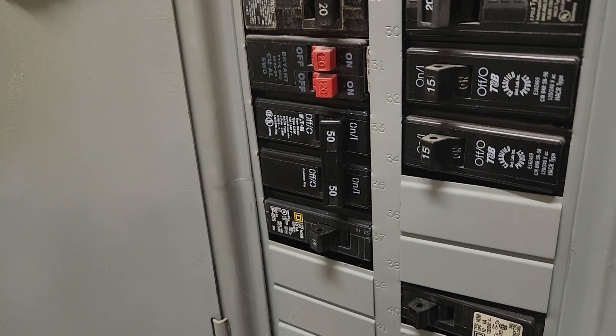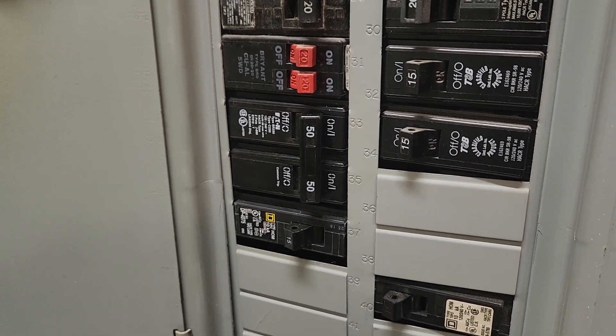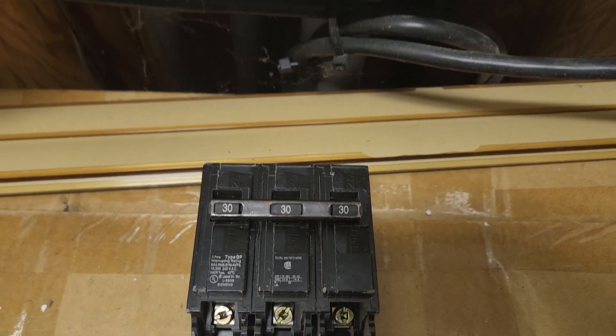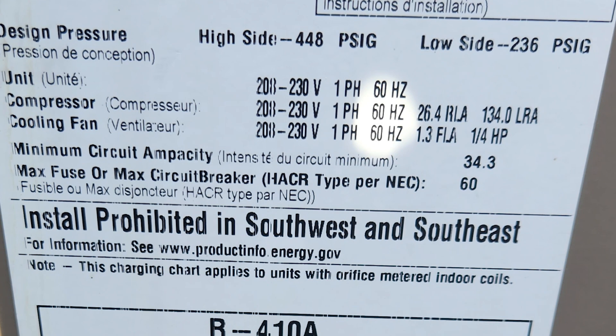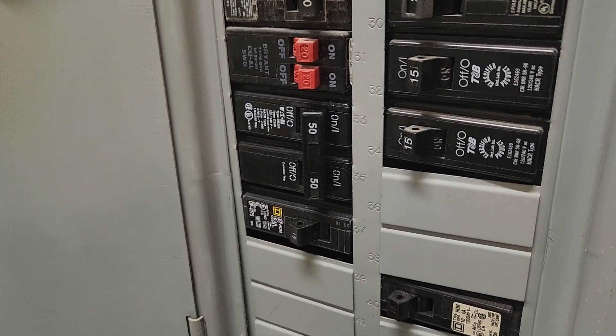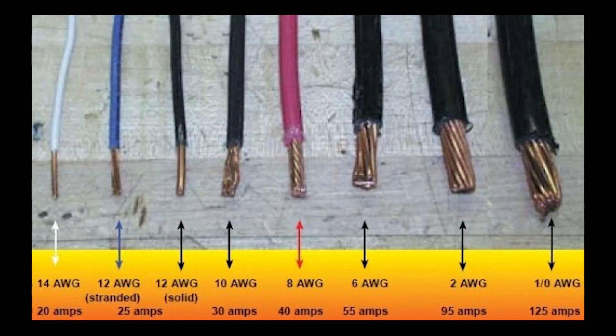The first real issue we ran into was that the circuit breaker was tripping. This was an easy fix. The breaker feeding the compressor was actually a 30 amp breaker, and the problem was immediately obvious — the minimum amp rating on the compressor is 34 amps and the max breaker size on that sticker is 60 amps. So I replaced it with a 50 amp breaker, which was fine since the existing wiring was six gauge and it can handle that load. If we had something like 10 gauge in there, we would have had to rerun that wire prior to upgrading the breaker.